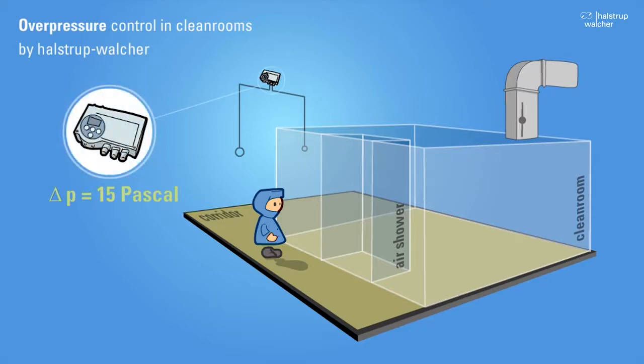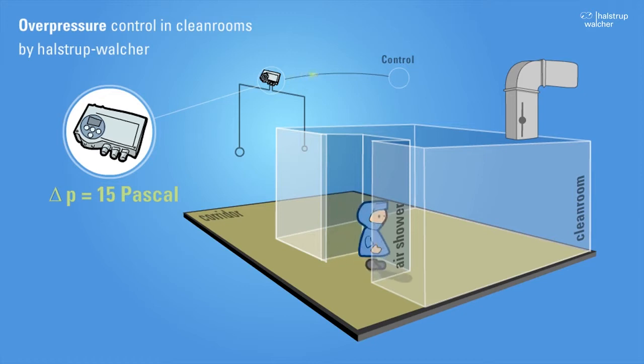This example clearly illustrates the mechanism used to maintain a positive pressure within the clean room. A high-precision differential pressure transmitter from Halstrup-Walcher continuously monitors the pressure and sends readings to the control system.